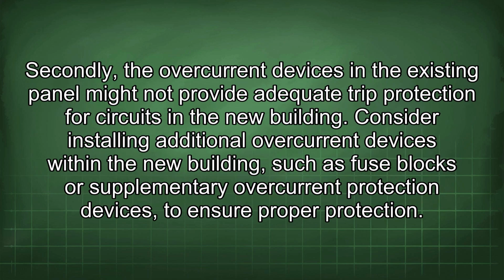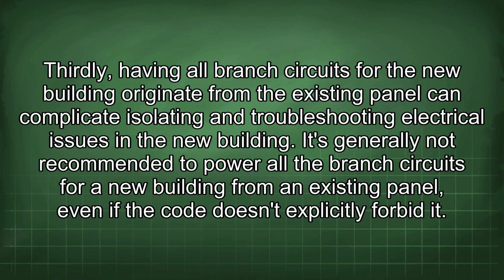Secondly, the overcurrent devices in the existing panel might not provide adequate trip protection for circuits in the new building. Consider installing additional overcurrent devices within the new building, such as fuse blocks or supplementary overcurrent protection devices, to ensure proper protection. Thirdly, having all branch circuits for the new building originate from the existing panel can complicate isolating and troubleshooting electrical issues in the new building.